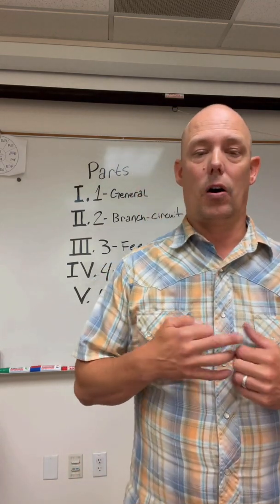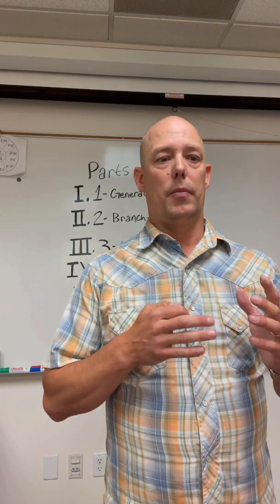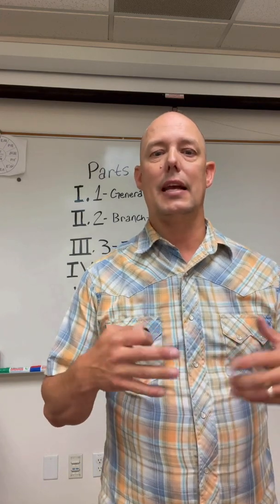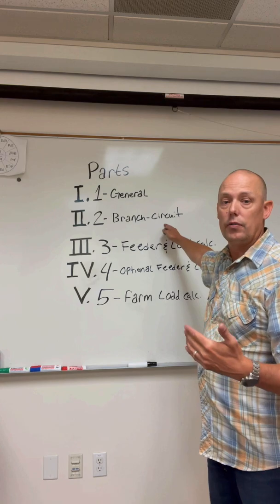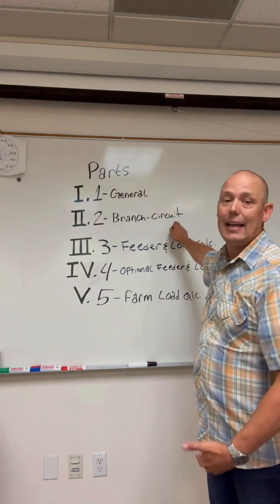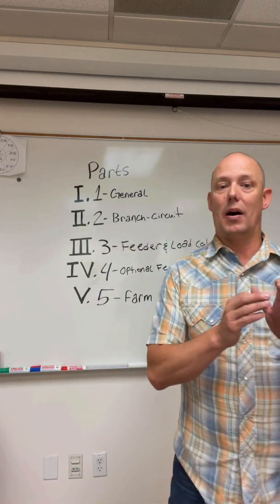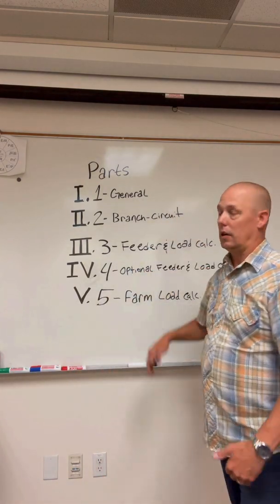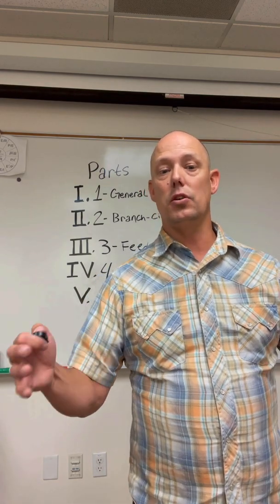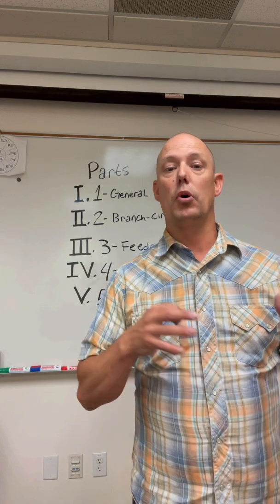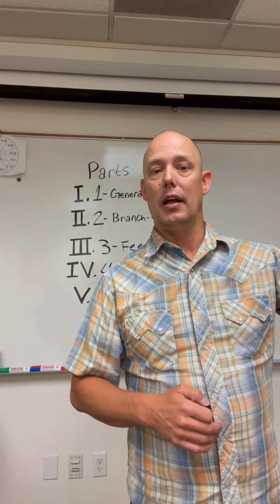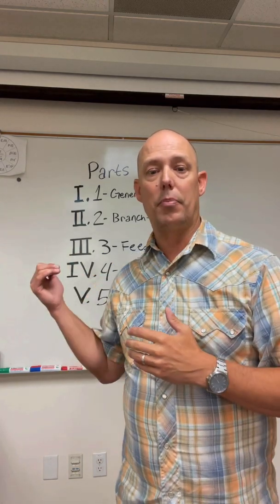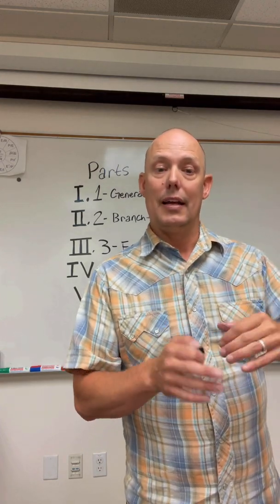Here's something important. I had a guy call me and say, why is it that they talk about show windows in Article 220? He said it's in 220.14G and 220.43, and they say the same thing — what's the point? Well, 220.14G is telling us that a show window has 200 volt-amps per linear foot for adding a branch circuit to an existing service, because we're in part two — it's talking about adding a branch circuit. Part three in 220.43 is talking about sizing the service. It still says 200 volt-amps per linear foot, so they say the same thing and it seems like it's repeating itself, but it's not — you're talking about two different areas. One is adding a branch circuit and the other is sizing a service. So understand the parts and where you're at in the article and chapter.